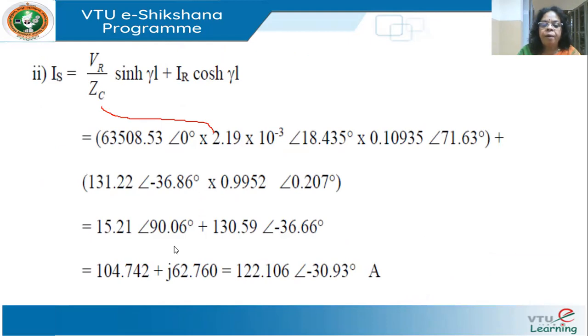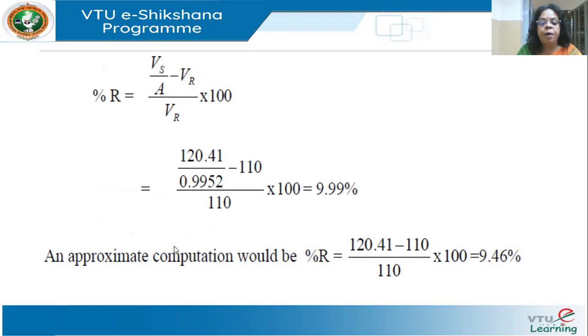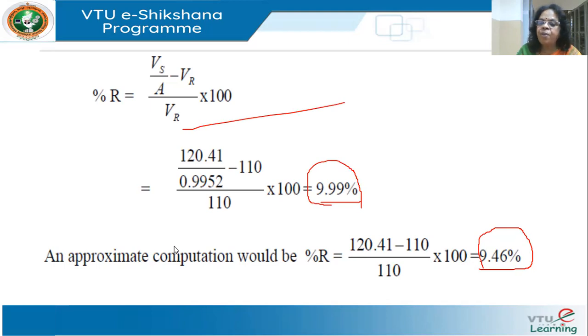Percentage voltage regulation: for long lines use (|VS/A| - |VR|)/|VR| × 100, giving 9.99%. The approximate formula (|VS| - |VR|)/|VR| × 100 gives 9.46%. The rigorous formula uses VS/A as the no-load receiving end voltage, which is more accurate for long lines since the difference can be substantial.